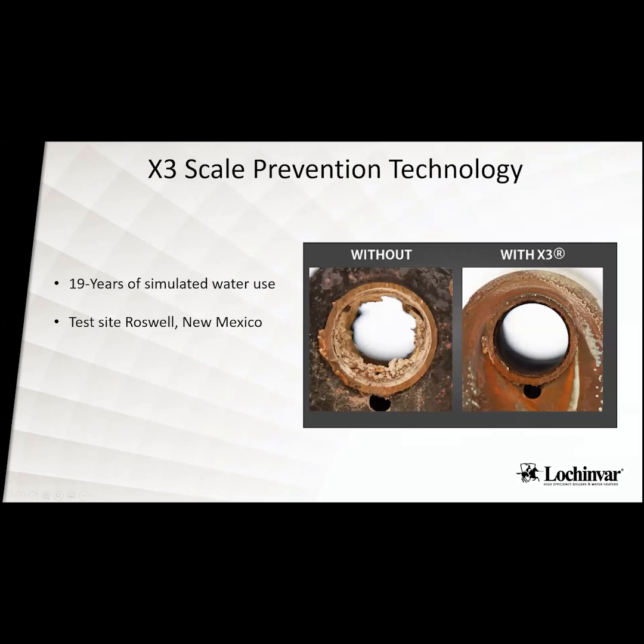So this is showing with and without the X3 technology. This is done in our test site in Roswell, New Mexico. This is done between 50 to 80 grains of hardness. Their water there is already hard enough, but when they do their testing, they're adding 40 pounds of salt per hour into the water that's recirculating through these units. So they get up to 80 grains hardness. The X3 that you see on the right side, that's that tube with 19 years of simulated usage. And the one here on the left was about 5 years of simulated usage before it scaled up and failed. So that is what that X3 technology will do inside of that unit.